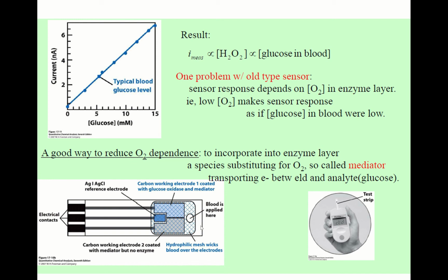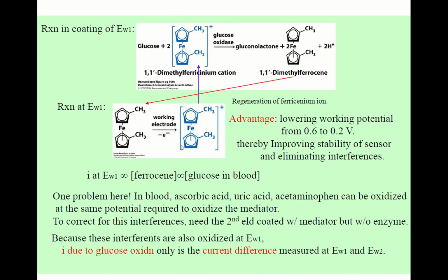Blood is applied here, and blood now is a liquid. Now it is sucked to this working electrode. Okay, and then what's the principle of this mediator type glucose sensor? Look at that. This ferrocene is one of the mediators.